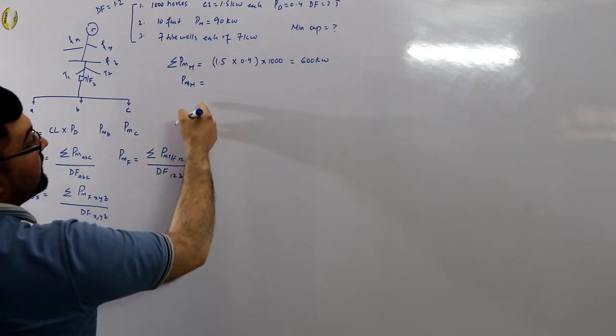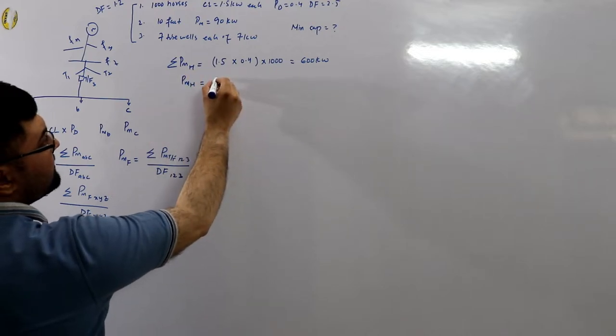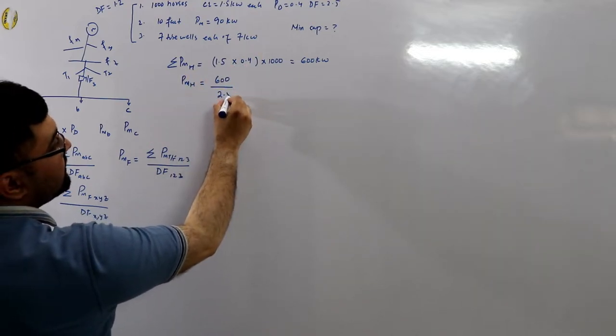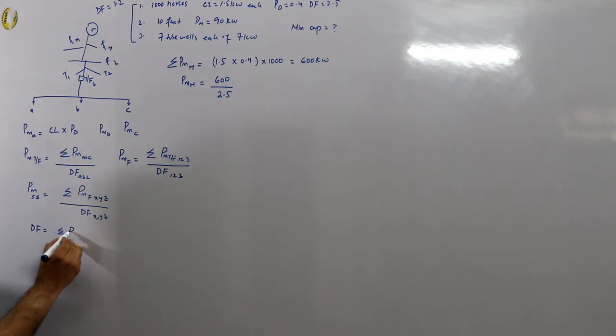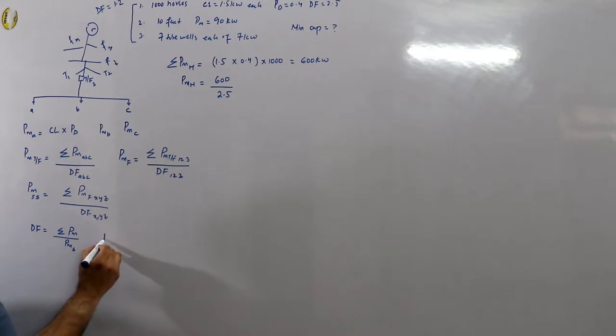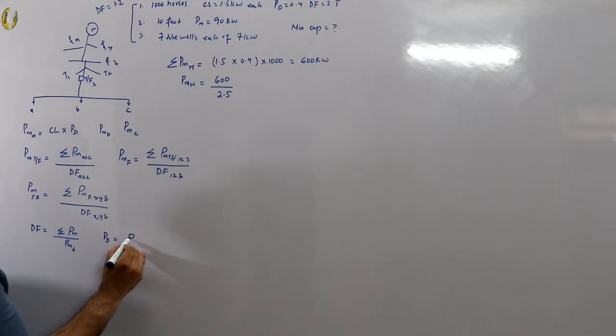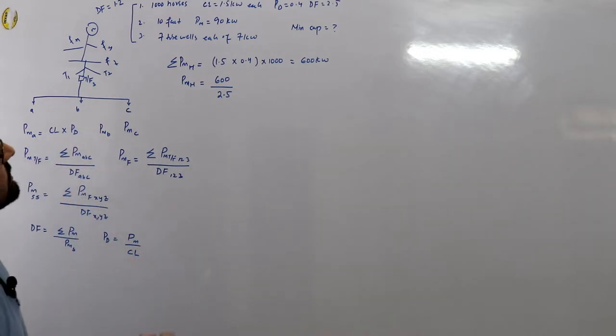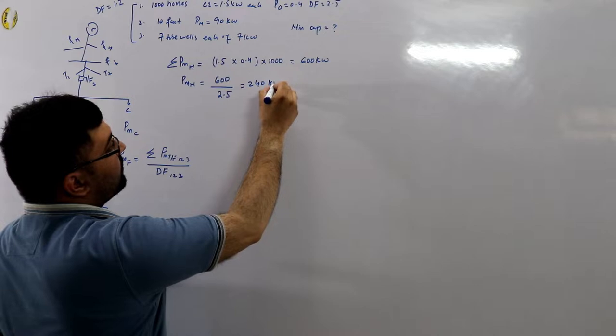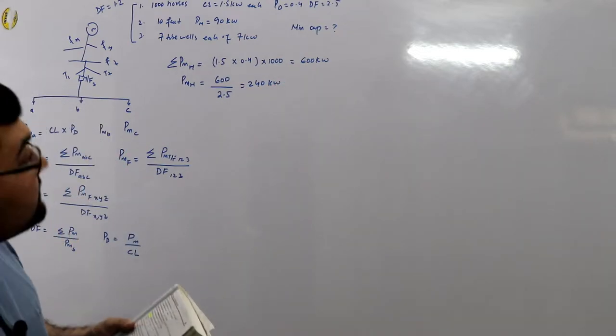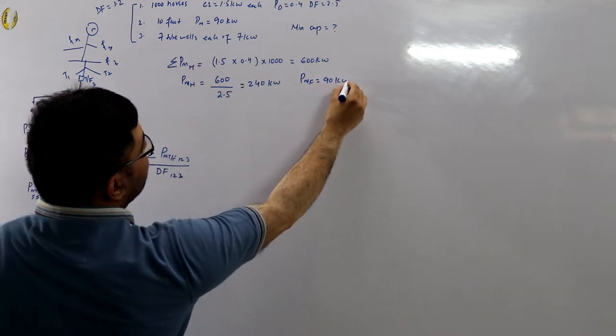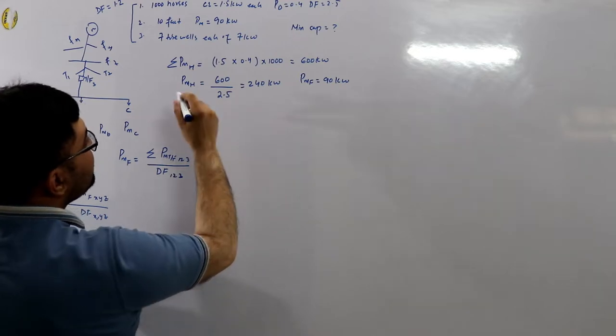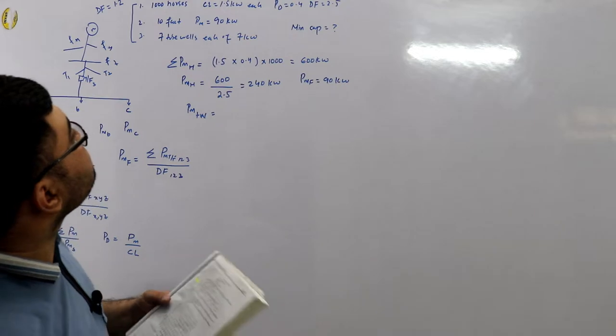The average maximum demand of the houses is 600 divided by the diversity factor 2.5, which gives 240 kilowatts. The maximum demand of the factories is already given as 90 kilowatts. For the tube wells, 7 kilowatts each and all operating simultaneously, so diversity factor is 1 — connected load is taken as maximum demand — giving 7 × 7 = 49 kilowatts.